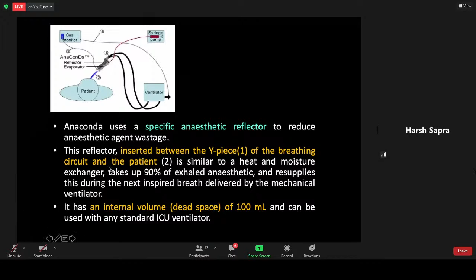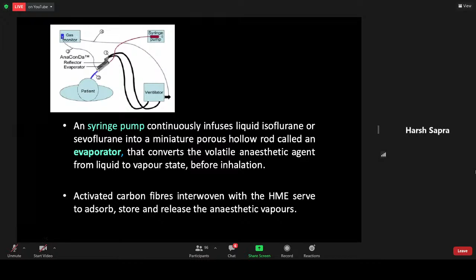And a syringe pump continuously infuses liquid isoflurane or sevoflurane into a miniature porous hollow rod called the evaporator, which is at the base of the Anaconda device. That converts the volatile anesthetic agent from liquid to vapor state before inhalation. And activated carbon fibers interwoven in the HME serve to adsorb, store, and release the anesthetic vapors. A sampling port from the Anaconda device allows the expired gas concentration to be continuously displayed on the gas monitor.